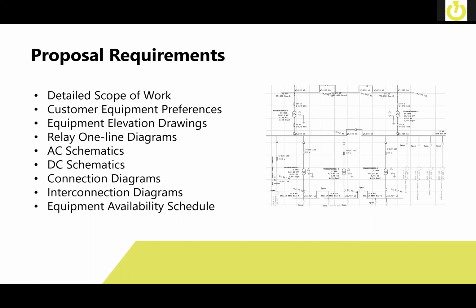So that equipment availability schedule, if we find out that we have to mobilize 5 times because the equipment's not going to be available on a continuous basis, that can all make a difference whenever it comes to the timing of the project, making sure we can meet your needs from a schedule standpoint, making sure that we can get enough people out there. If you're trying to do a 20 relay retrofit project, for instance, and you're trying to do all of that in a single night, which has happened before, we need to make sure that we have enough people available, and we also optimize the design to be able to do that in a quick fashion.